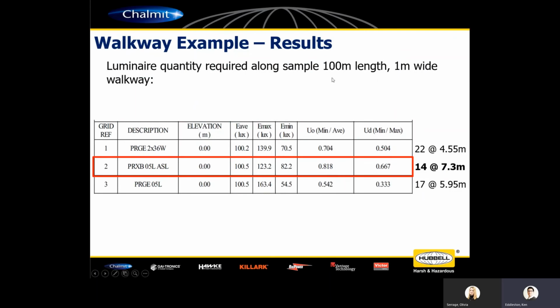Looking again at this 100 meter length, if you're looking at 50% as emergency, you still need 11 emergencies on the Protecta fluorescent, but you can get away with 7 emergencies on Protecta X. I'm sure you're aware the emergency version tends to be the more premium option, because of the battery pack, inverter, and intelligence within the product. So if you can reduce your overall emergencies required in your project, that's a massive saving as well.